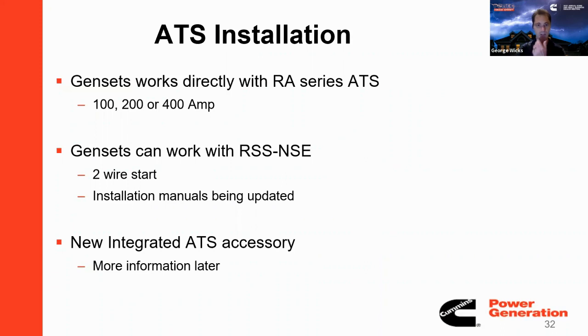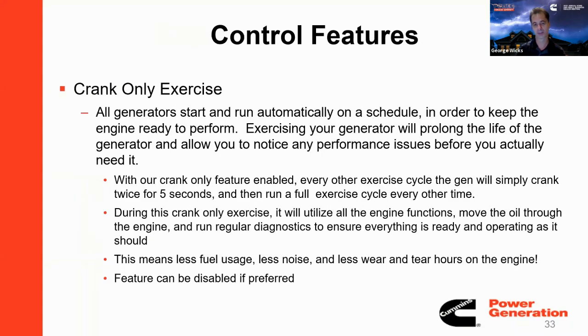And the transfer switches that work with these are our RA series. They work with all of our liquid cooled models all the way to 100 kilowatts. So it's one transfer switch, 100, 200, 400 amp. Easy to stock them, easy to sell them. Installation and wiring is identical. That's just a 2-wire start, and any 2-wire start transfer switch out there will work with these generators. So the generator can basically be replaced without the switch gear on the wall being replaced. That's a nice feature, because we do come across those old units that need to be replaced, but not the wiring and the switches.